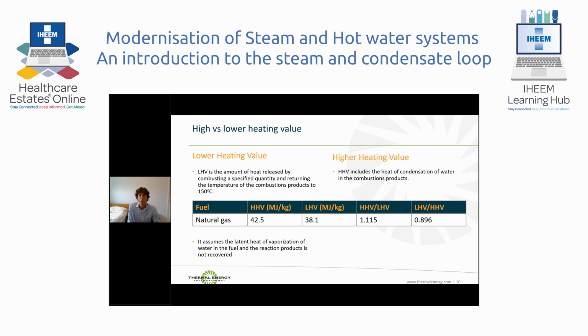Burning natural gas, CH4, the products of combustion are H2O and CO2. In the UK, the convention is to rate boiler efficiency on the lower heating value of the fuel, which hides the wet losses available when you condense the exhaust. This is a hangover from burning coal and other dirty fuels, which are designed to operate above the acid dew point. As you can see here, for natural gas, there's a considerable difference between the lower heating value and the higher heating value. If we were to rate up to recover all of the energy from the higher heating value, we get an extra 11.5% of energy out of our fuel.